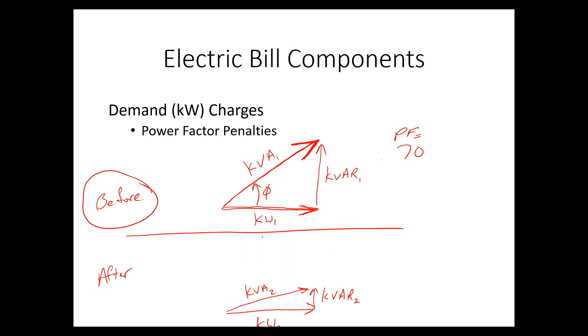And what we want to do is install capacitors, which would basically be a force, a vector fighting this KVAR, it would be a vector down, such that in the after scenario, our KVAR2 is much less than our KVAR1, and thus our KVA2 would be much less than our KVA1 to deliver the same amount of work. So KW1 equals KW2. The work is the same, but the amount that the utility has to do is less.